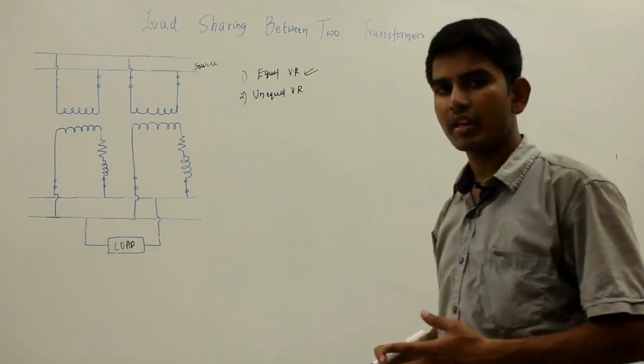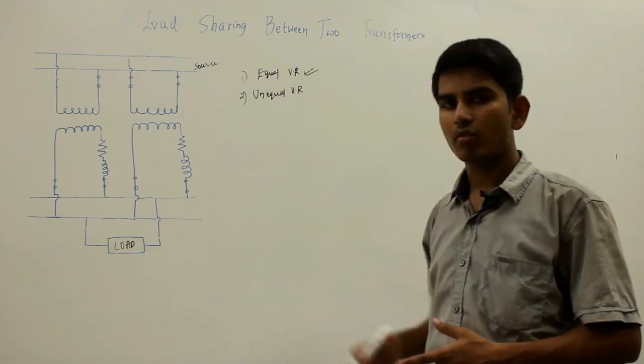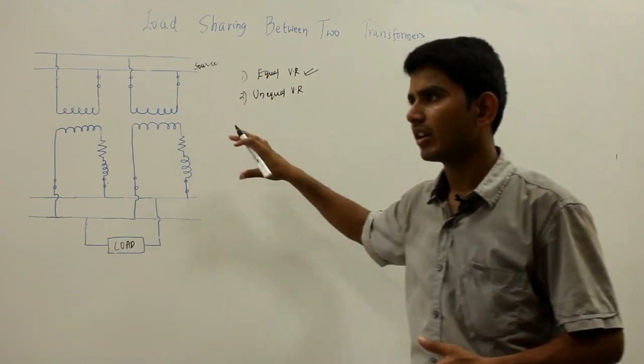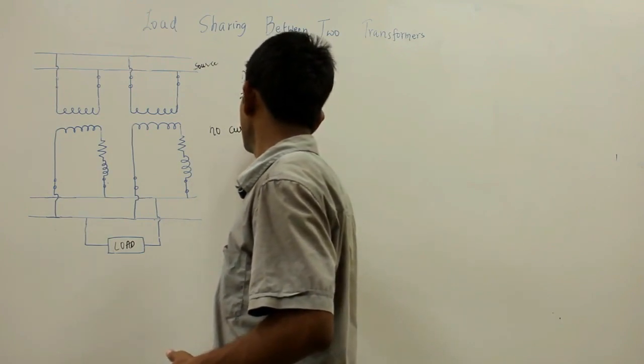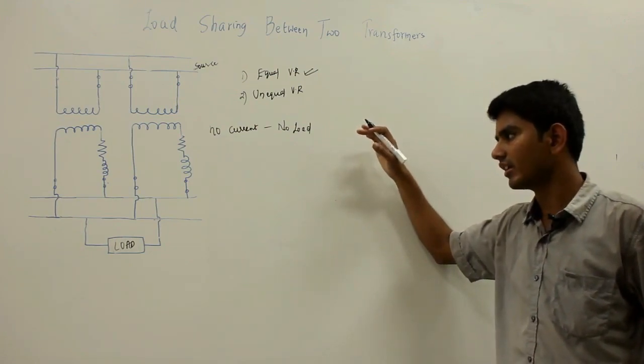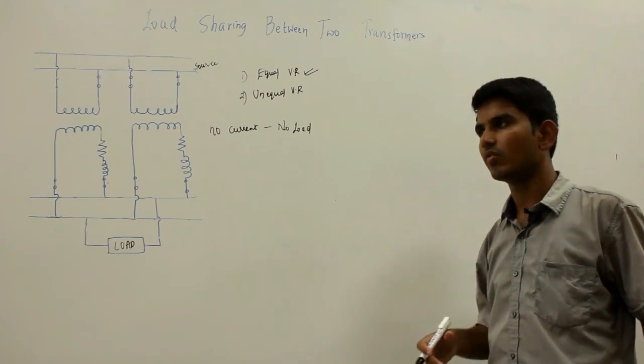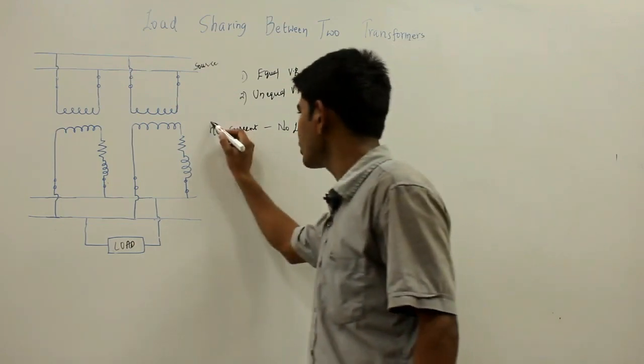Let us first discuss the equal voltage ratio case. If the two transformers have equal voltage ratio and voltages are in phase, then the primary side and secondary side can be connected to operate in parallel, and no current will flow during the no-load condition. If they are on an unequal voltage ratio, they will have a large circulating current in the secondary and primary sides, and that current will be very high compared to the no-load current as the leakage impedance on load decreases, giving a high value of circulating current. With equal voltage ratio, there is no circulating current at no load.